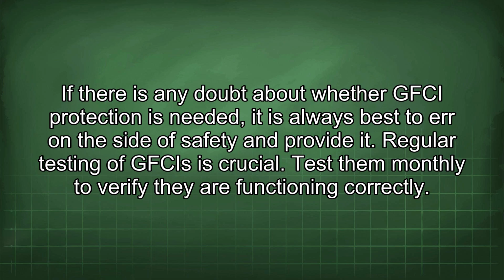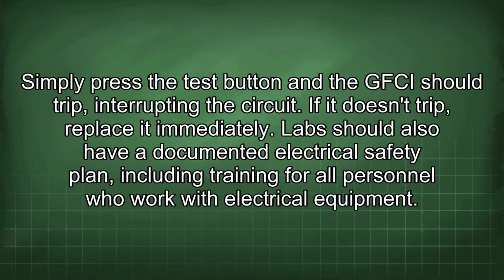Regular testing of GFCIs is crucial. Test them monthly to verify they are functioning correctly. Simply press the test button and the GFCI should trip, interrupting the circuit. If it doesn't trip, replace it immediately.